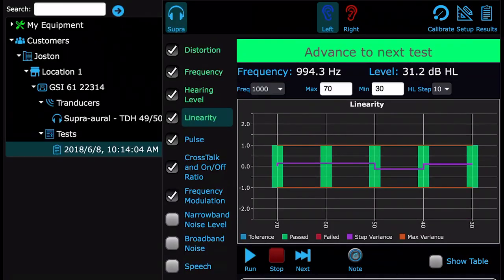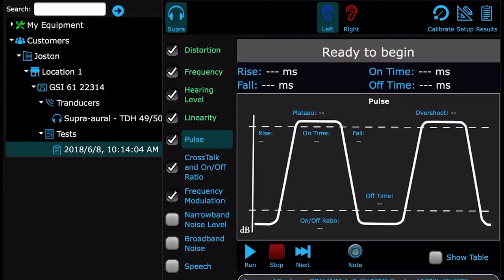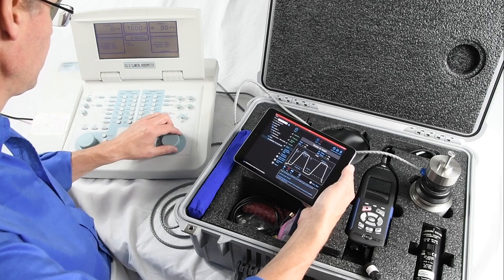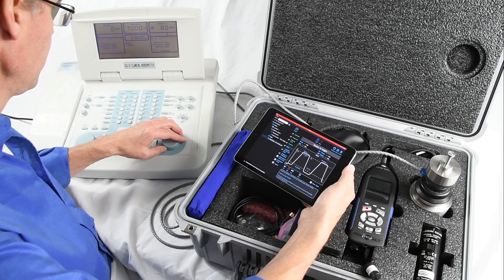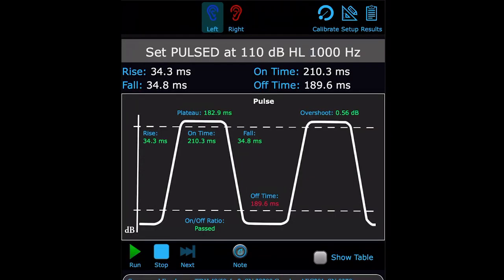The next test, Pulse, is a quick test and requires that the audiometer mode be set to pulsed tones. In just an instant after pressing Run, the results are calculated. This audiometer failed in the off times for that frequency. This test can be rerun just like any test at any time.